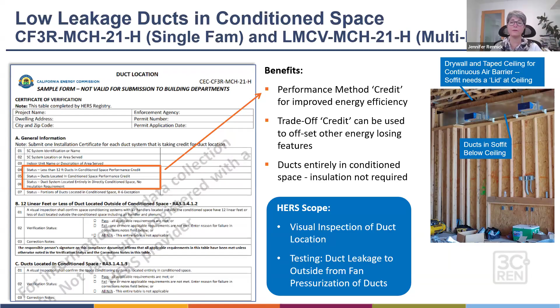And then, for example, if you clicked or triggered one of those HERS measures where the duct leakage diagnostic testing is needed, like we said, the low leakage ducts in conditioned space, then once the system is built up and the envelope is taped, sealed, ready to go, then the HERS raters can come out and put their flow and pressure gauge onto the duct system and cover the supply ducts with these special caps, or tape it off and seal it so that they can really just get a good pressure reading on the ducts and prove that the ducts aren't leaking.